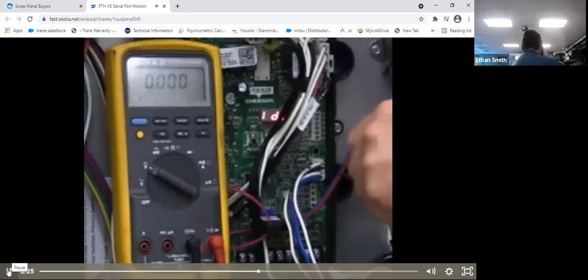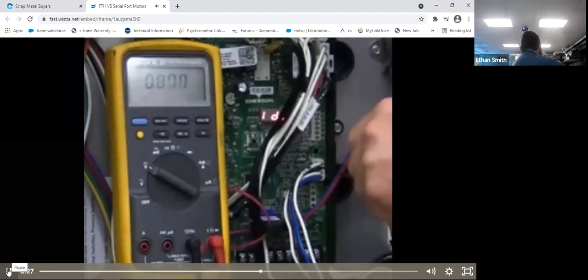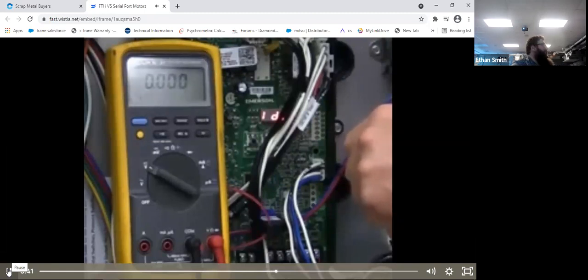And I can see my TX here is pulsating about once a second. And it's going to run between 0.7 to 1 volt DC from what I can read on the meter. If I'm looking at an air handler control board, I'm going to see the pulse speed much more rapid, and I will see several packets being transferred every second. So the frequency of the pulse is not important. The fact that we are seeing pulses and voltages confirms that the control board is sending data to the motor.